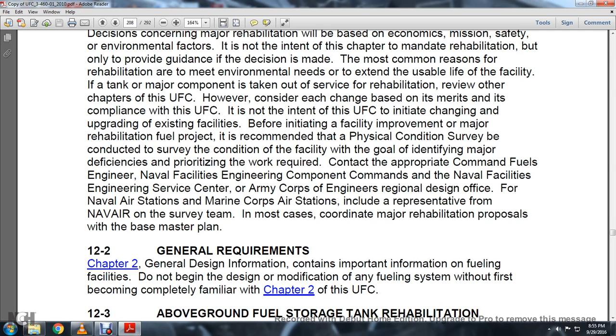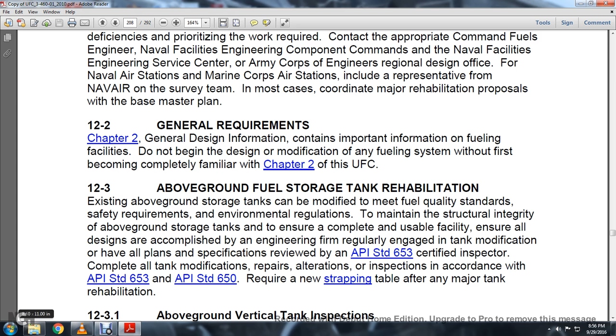12.3 Aboveground Fuel Storage Tank Rehabilitation. Existing aboveground tanks can be modified to meet fuel quality standards, safety requirements, and environmental regulations, and to maintain structural integrity. To ensure a complete and usable facility, all design and engineering should be accomplished by personnel familiar with tank modification, and all specifications should be reviewed. Have an API Standard 653 certified inspector complete all tank modifications, repairs, alterations, and inspections in accordance with API Standard 653 and API Standard 650.